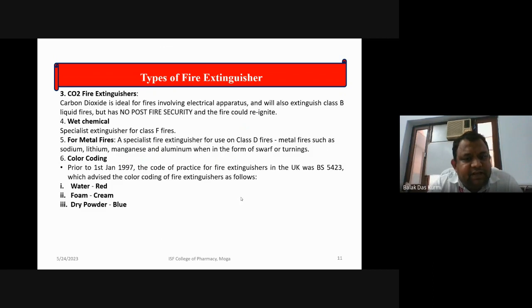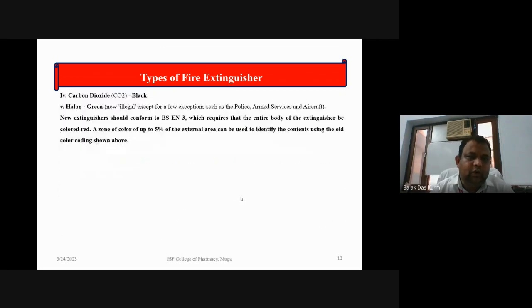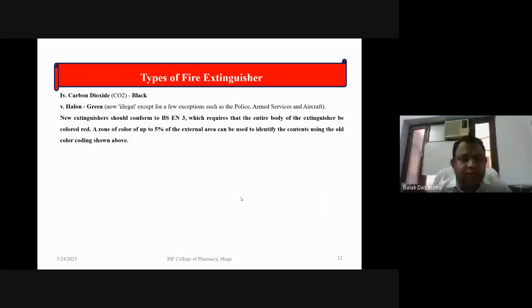Color coding: prior to 1st January 1997, the code of practice for fire extinguishers in the UK was BS 5423, which advised the color coding of fire extinguishers as follows: water, red; foam, cream; dry powder, blue; carbon dioxide, black; halon, green. Now halon is illegal except for a few exceptions such as police, armed forces, and aircraft. New extinguishers should conform to BS EN 3, which requires that the entire body of the extinguisher be colored red. A zone of color of up to 5% of the external area can be used to identify the content using the old color coding shown above.